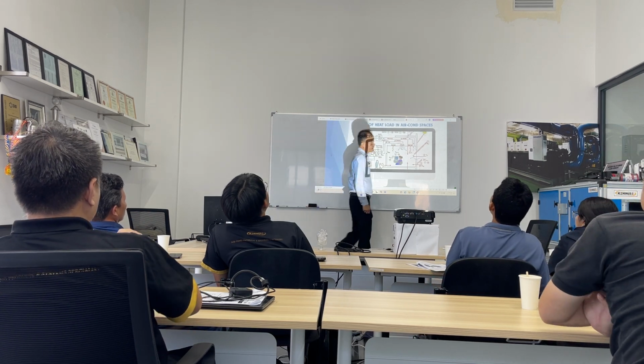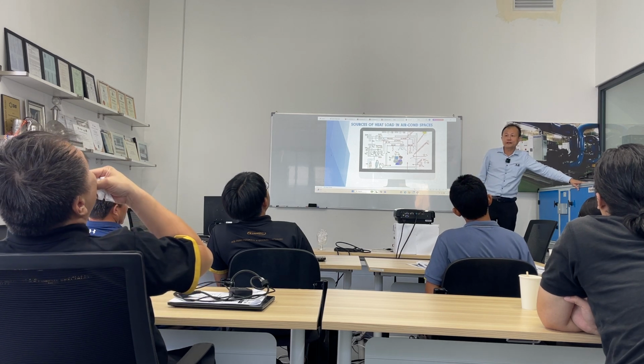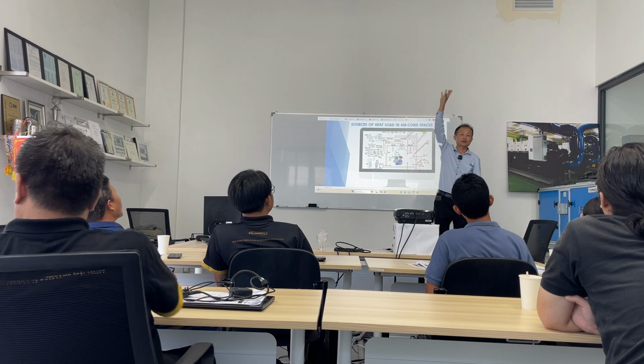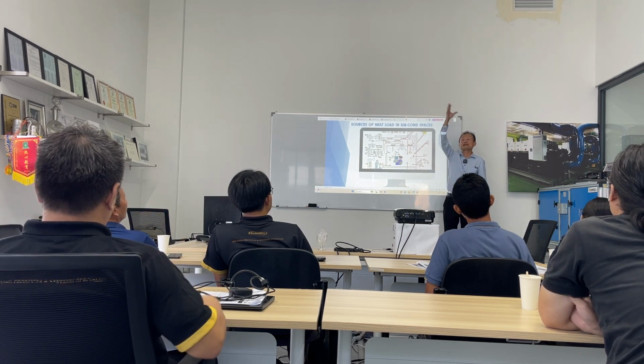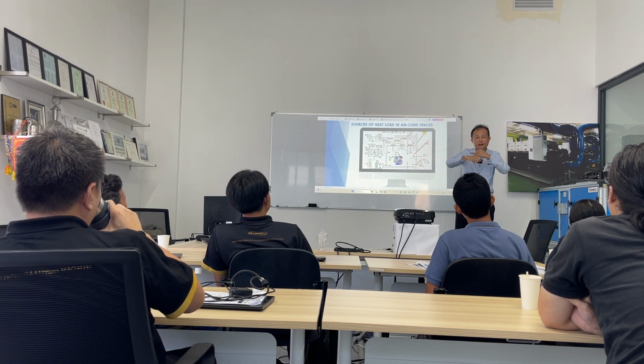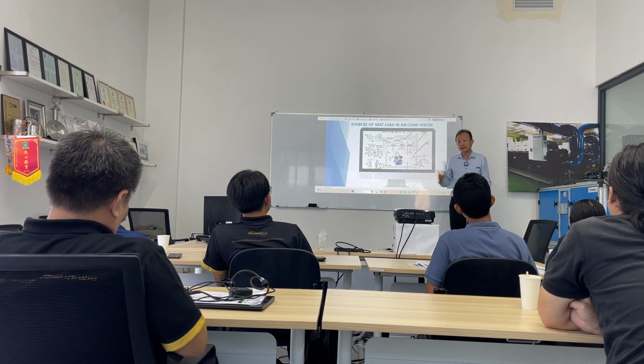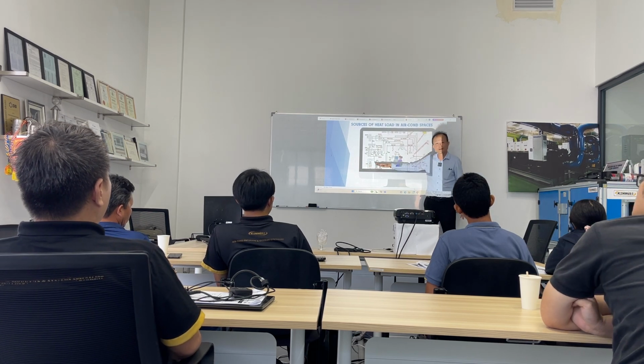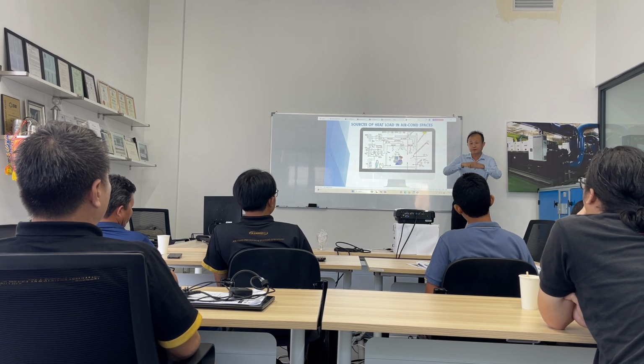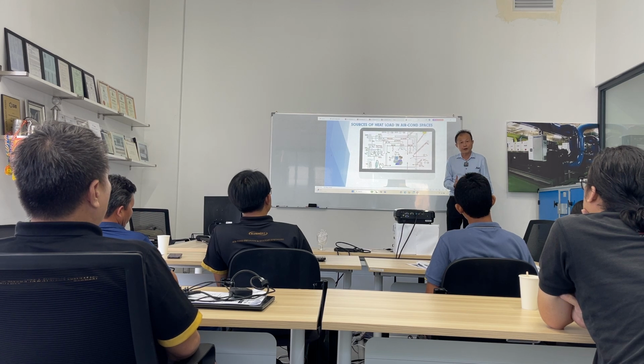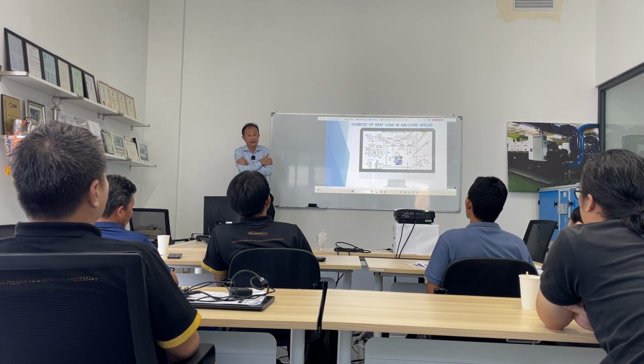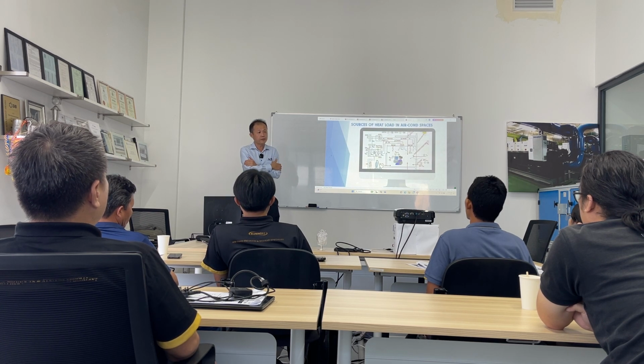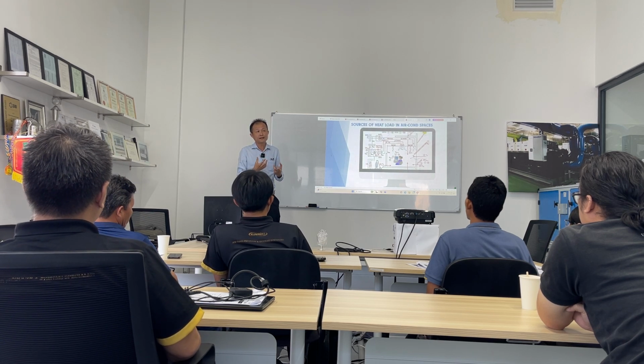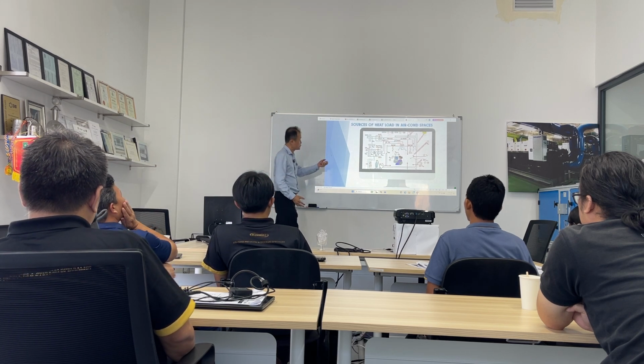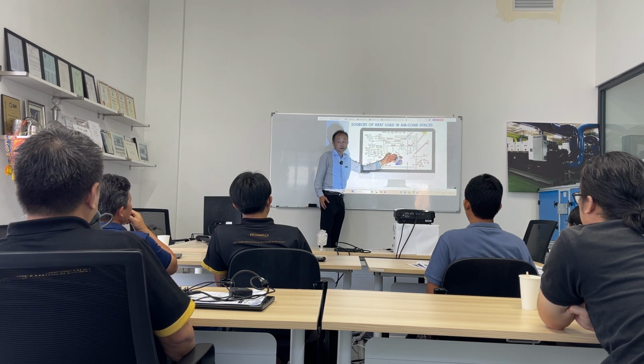So of course, these are one of the units that deliver the air inside the building. Of course, inside here there is a cooling coil. In this basic system, you cannot see that during the delivery of the cooling medium through the entire process, there are some losses. These losses also generate heat for the aircon. That's why you see these components, later I will explain to you: the piping, the pump, the fan, the blower, the motor running also generate heat. So these are also components of heat that the aircon needs to take care of. Okay. So through this slide, you can see the overview of all the various components of heat that is being generated inside the space and also through delivering the cooling mediums into the aircon space.